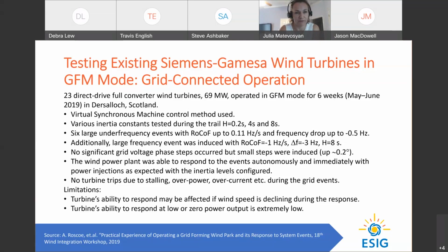They survived 6 large under frequency events that happened on the grid during the testing period. The largest one had a rate of change of frequency of up to 110 millihertz per second, and a frequency drop of 0.5 hertz. Additionally, they wanted to simulate a larger frequency event with a rate of change of frequency of 1 hertz per second. This is the requirement that GB is heading towards, with a frequency deviation of 3 hertz. They tested it with an inertia constant of 8 seconds on grid forming inverters. There were no significant grid voltage phase steps; the largest that they tested was 0.2 degrees. The wind plant was able to respond to all events autonomously and immediately with power injection as expected, with the inertia constant as configured. They didn't have turbine trips due to stalling, overpower, or overcurrent during all of these grid events.